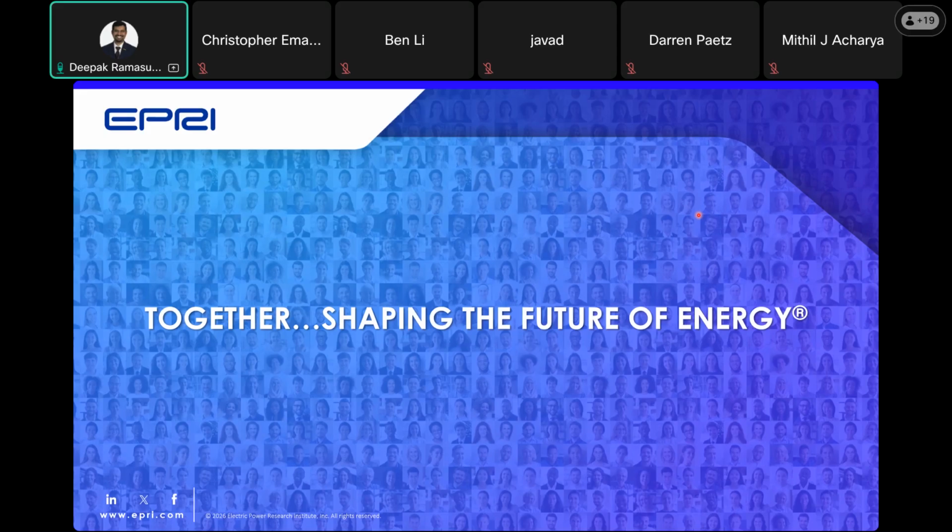If you look at the UNIFI specifications version 3 that was released earlier this year, we've identified certain thresholds and test criteria that can help determine whether voltage frequency control is being provided or active power frequency control.